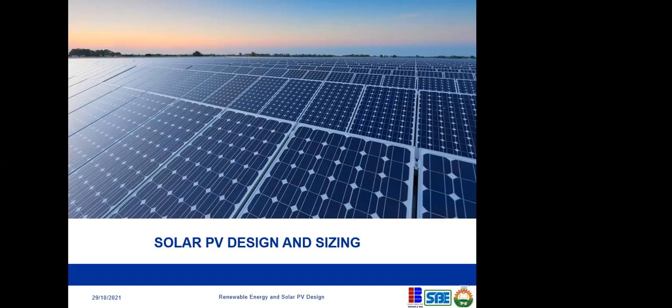I think this will depend on the designs we are looking at. Firstly, if you look at what our daytime load is and what our night load is, I personally think we can size our system to meet our daytime load, while the battery backup serves the night load. Some designs can have a panel array sized up to your daytime load, with minimal backup for the night load, so that the cost of batteries is not so high.